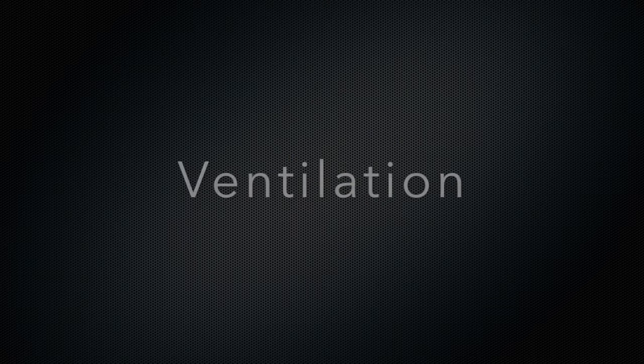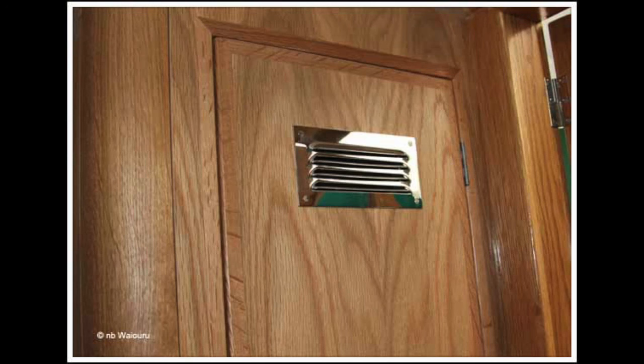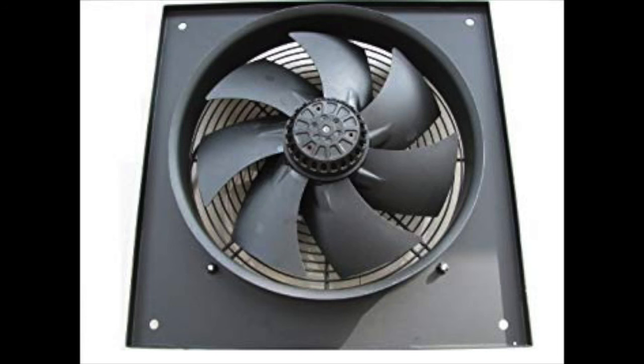Ventilation: If the steam generator has been boxed in, you must allow ventilation using a vent grill. For commercial operation, especially in plant rooms, we advise mechanical extraction fans to be running at all times to lower humidity and temperature which can cause premature failure to electronics.